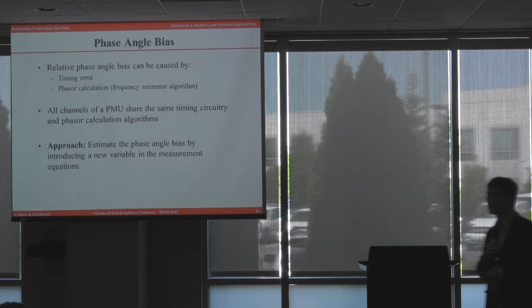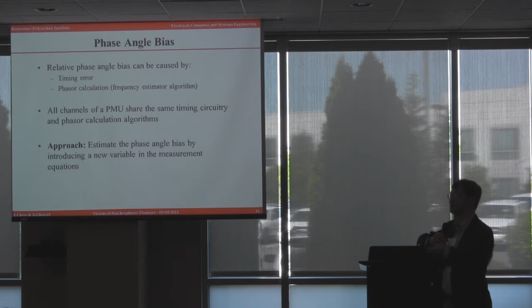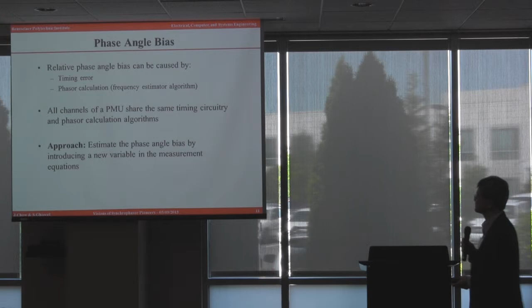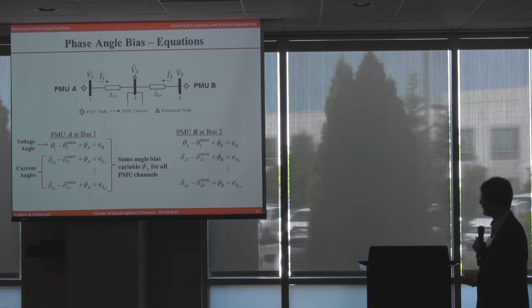And we found that we were consistently puzzled by these phase angle biases. We think that there could be timing error in whatever internal calculations, or maybe the length of the instrument cable and so on. But one thing that we feel is useful information is that if you see a phase bias in one channel of a PMU from a location, you can count on the fact that it will show up in all other channels, because they use the same timing signal, the same FFT calculations and the same filter, and we can just pick up the difference. It simply is the fact that you introduce these additional angles that you can correct.